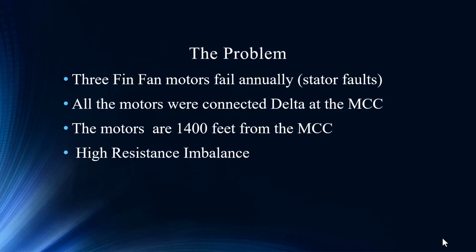They're 200 horsepower, so those are expensive motors. This is excessive. This is not what you'd expect. I mean, these a lot of times are gear driven. There's gears in between the motor and the fan. Not exactly sure about this application, but they change from location to location. But three times a year is a lot.